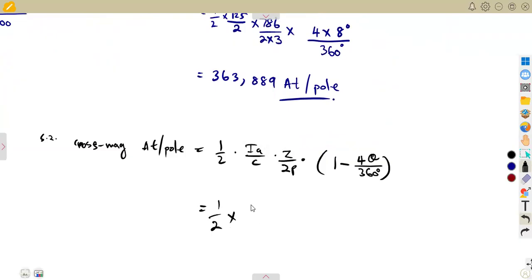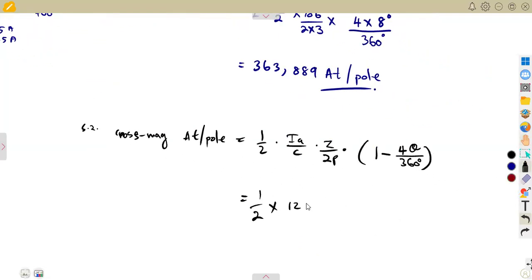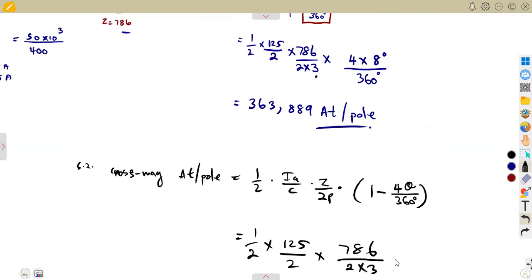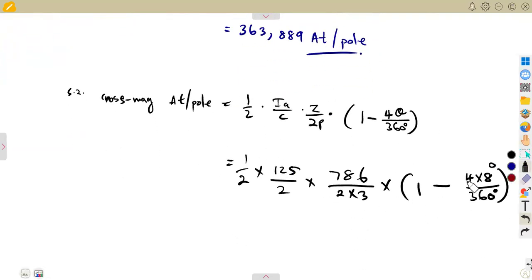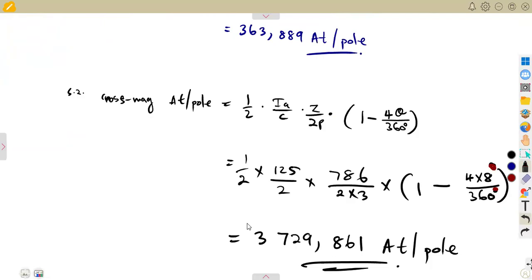We already calculated the base values. So cross-magnetizing AT/pole = one-half times 125, over C (2), times Z (786) over 2P (3), times one minus four times 8 degrees over 360 degrees. This gives us 3,729.861 ampere-turns per pole. That is the cross-magnetizing result.